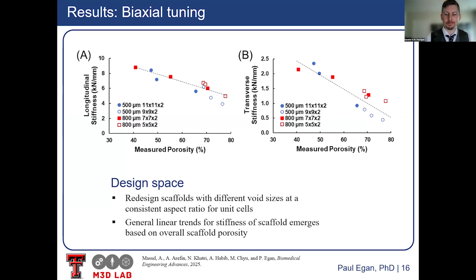And then to finish off this study, we mapped them to the stiffness. So we created the lattices of all different porosities and beam diameters that we could configure with the different hierarchical pore size. And we found a general trend that no matter what the design change you did, generally, as you increase the porosity, you're going to decrease the stiffness, but you can tune this based on your exact patient needs. So how big the implant needs to be, how heavy that person is, their activity level, to get the stiffness that they would want for that application, but also keeping that good biological growth as well. And so now that we have these physically validated, we can bring in the computational design to navigate these trade-offs and try and get some optimal solution.